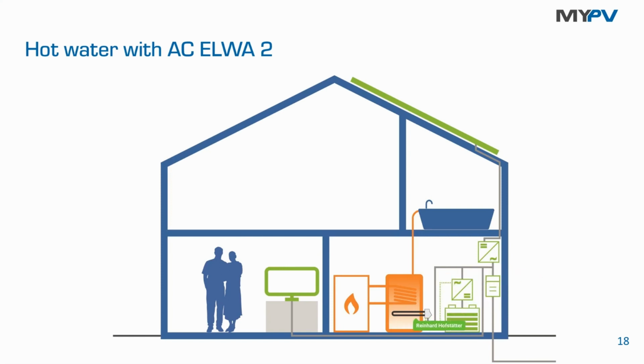And the linear power output can be changed from 0 to 3,500 watts. So AC ELWA 2 has a nominal maximum power output of 3.5 kilowatts. And from 3.5 kilowatts down to 0, every single watt here is possible thanks to the MyPV power electronics in the device. So it's adjusting the balance in the feed-in point 1 time per second, very fast and very accurate. All right.